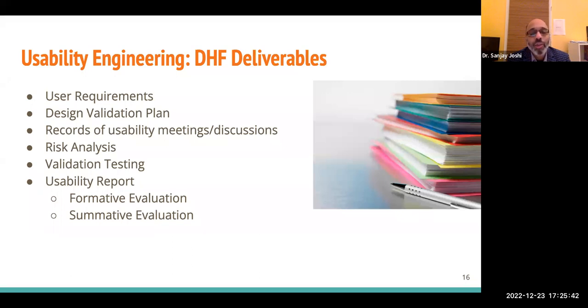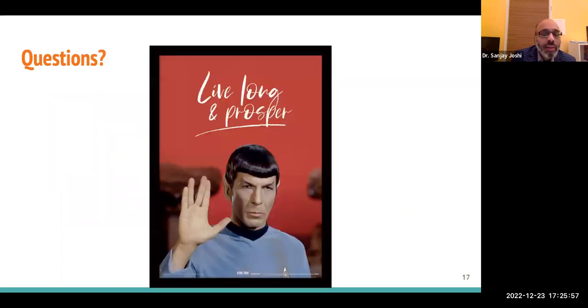And at the end, a usability report, a record of what kind of formative evaluation you did, what kind of summative evaluation you did, where are your hazards located, where are your use specifications located, and what's your ultimate conclusion. And that is pretty much it.